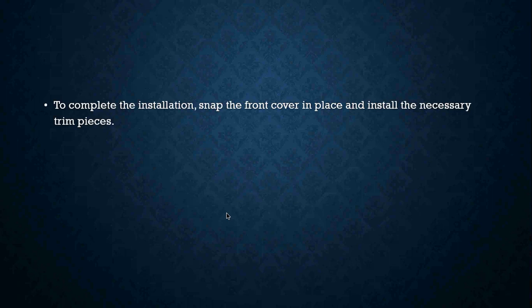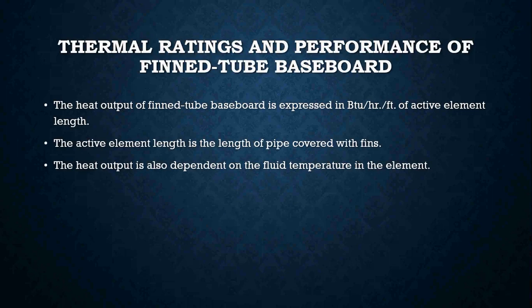To complete the installation, snap the front cover in place and install the necessary trim pieces. Regarding thermal ratings and performance of fin-tube baseboards: heat output is expressed in BTUs per hour per foot of active element length. The active element length is the actual length of baseboard that has aluminum fins on it — any area without aluminum fins is not considered active, because it is the aluminum that creates and generates the heat. Heat output is also dependent on the fluid temperature in the element.